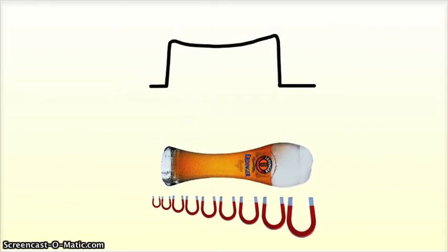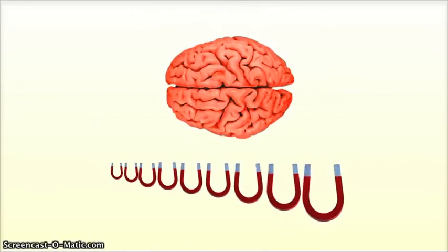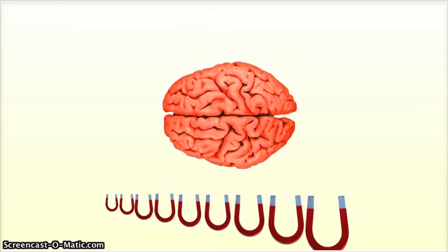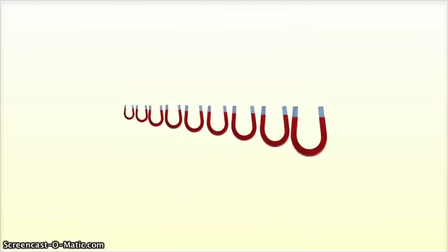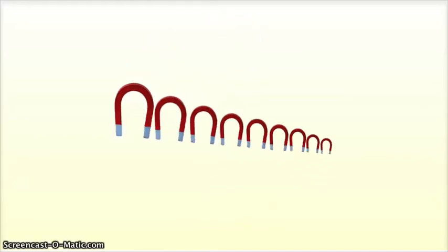So this is a good start. We've got a profile of our object, but let's face it, we wanted an image. So we've put our somewhat more realistic object this time into our magnetic field gradient, and we would like to see an image of it. So we take our gradient, and we rotate it. And then we get another profile of our object, but in a different direction, and we can keep rotating it and getting different profiles of our object.